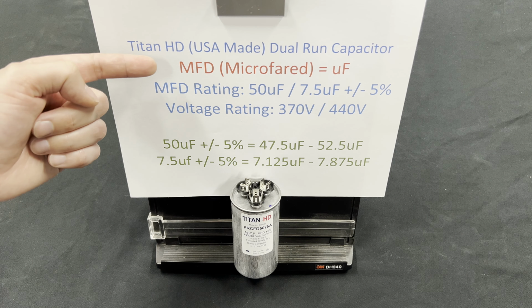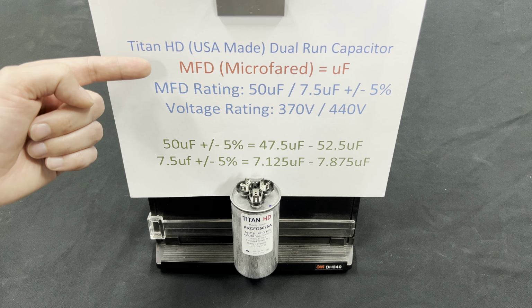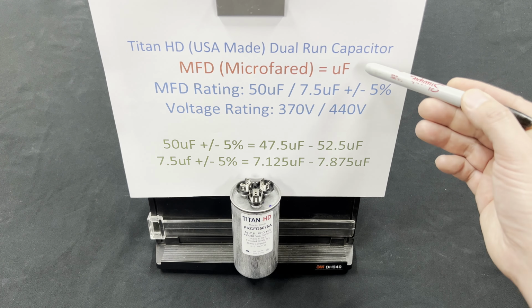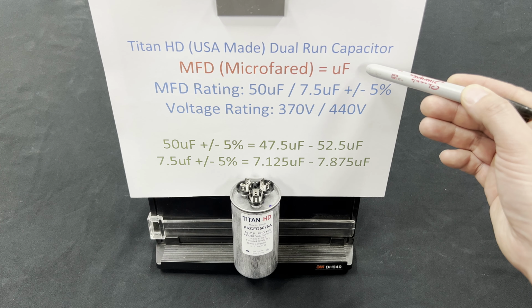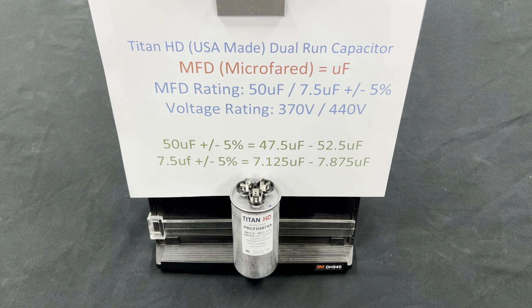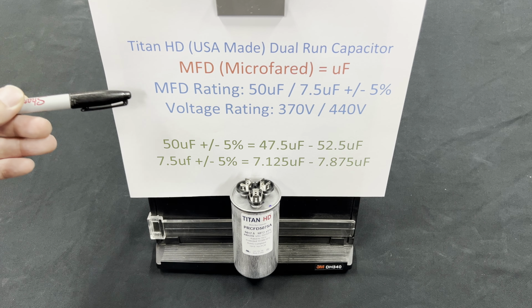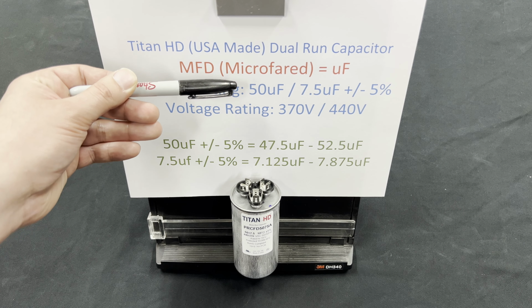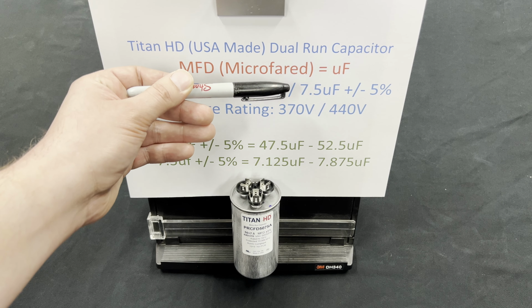Capacitors are rated in microfarads or MFD. The unit of measurement for that is UF. We'll be using this throughout the rest of the video. The MFD rating, like I'd mentioned, for this capacitor is 50 UF, which would be for the compressor, or 7.5 UF, which would be for the condenser fan motor, plus or minus 5%.